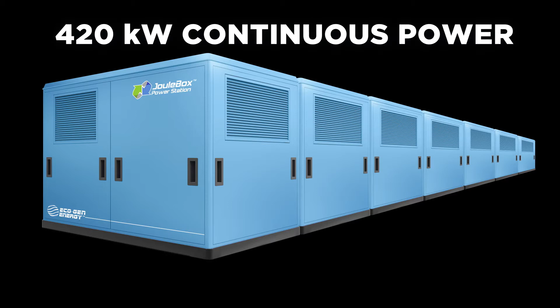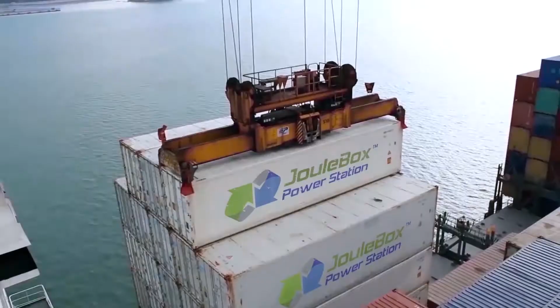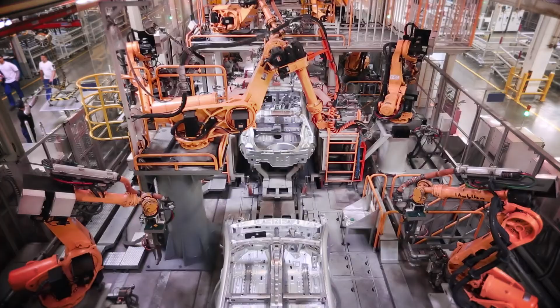For large installations, 7 Joule Box power stations are permanently installed in a shipping container and wired in the factory. When installed on site, they are either synchronized with each other or to the grid and locked down electronically. The containers can be double-stacked and wired together in parallel. The installations are scalable up to 50 megawatts or more of continuous electrical power. That's enough electric power to run a large manufacturing plant, or a university, or a small town, or even an island. It's a great solution for developing countries where there is limited access to fuels.